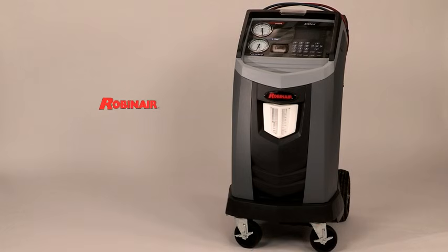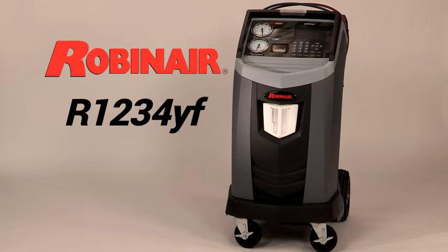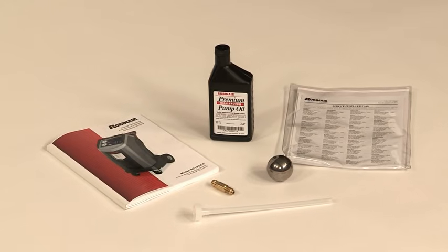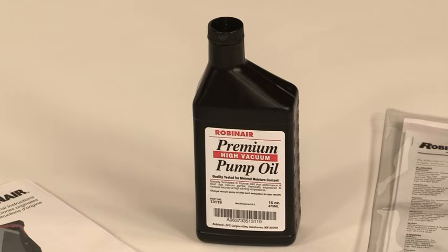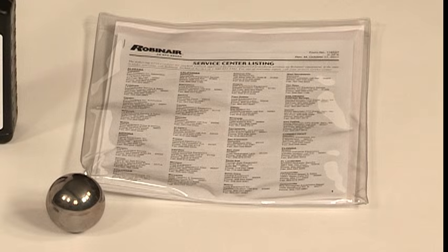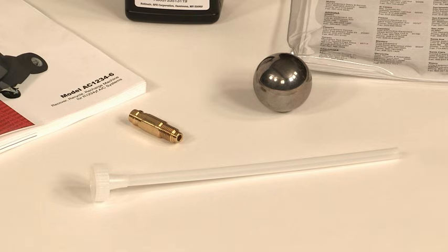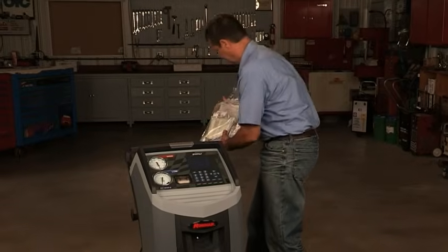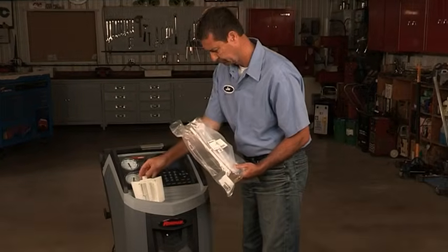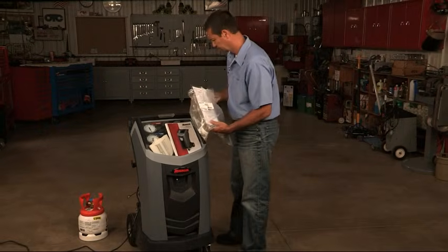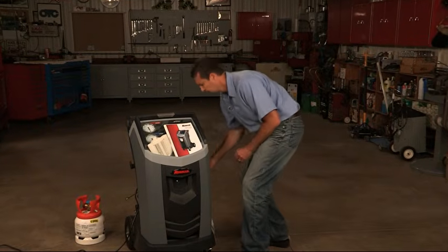Your new Robinair R1234yf is designed and certified to SAE J2843 HFO recovery, recycling, and recharging equipment standards for flammable refrigerants for mobile air conditioning systems. Ensure you read the owner's manual included in the accessory kit before setup. The kit also includes vacuum pump oil, the owner's manual, service center listing, calibration weight, tank fill hose adapter, and cap fill adapter. At this point, it is a good idea to install the oil drain bottle that is also included in the accessory kit.